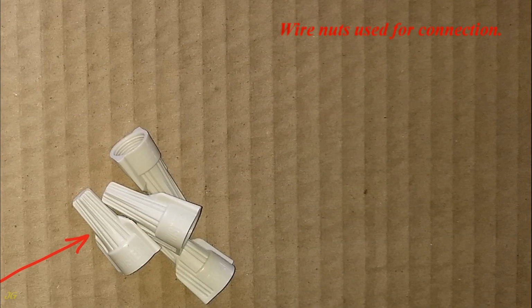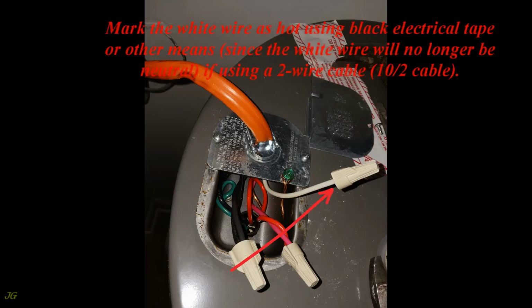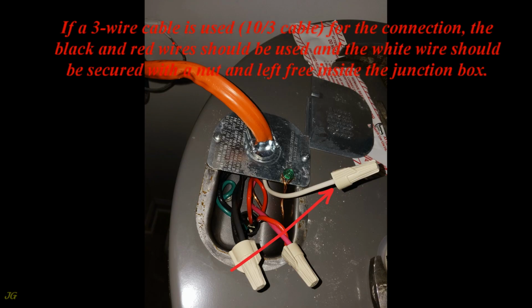Wire nut used for connection. Mark the white wire as hot using black electrical tape or other means, since the white wire will no longer be neutral if using a 2-wire cable, 10-2 cable. If a 3-wire cable is used, 10-3 cable, for the connection, the black and red wires should be used and the white wire should be secured with a nut and left free inside the junction box.